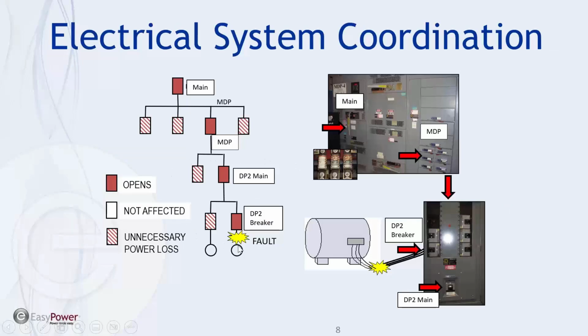So this is the kind of thing you have to be careful with in coordination: making sure that the breaker that has a fault is the breaker that's going to trip. You don't want a blow dryer in a bathroom killing the plant. It's not a good thing. Major outages like that can cause some major issues.